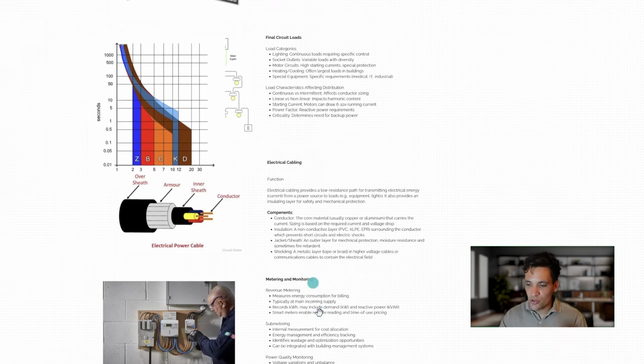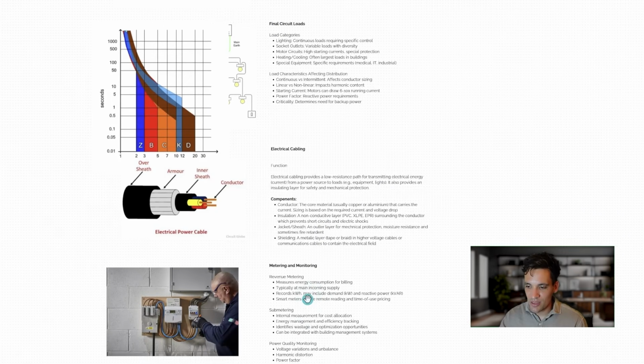And also critical to this system, we've got metering. So metering is basically the electricity authority's way of measuring how much electricity you're using so they can bill you for it. You can have revenue metering, which is on the main switchboard where you get the incoming power cable.